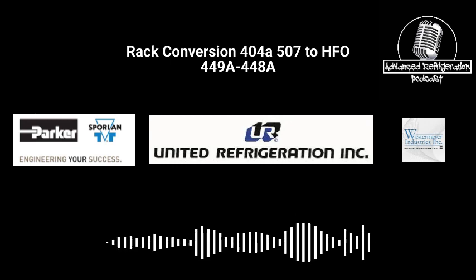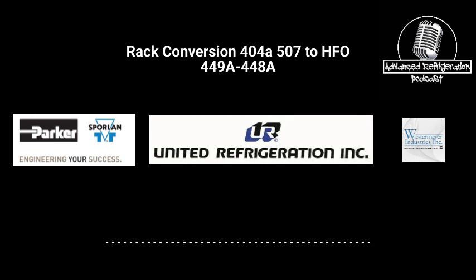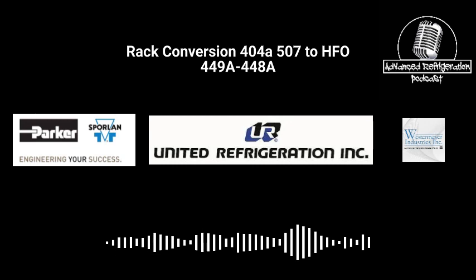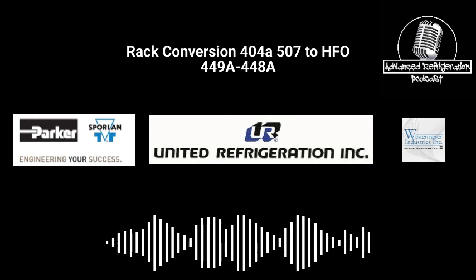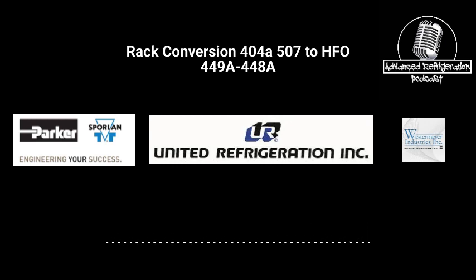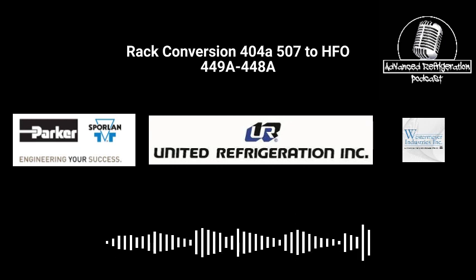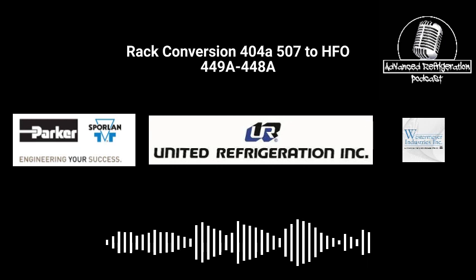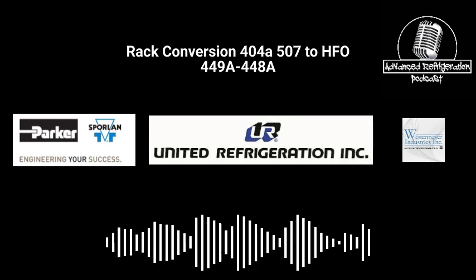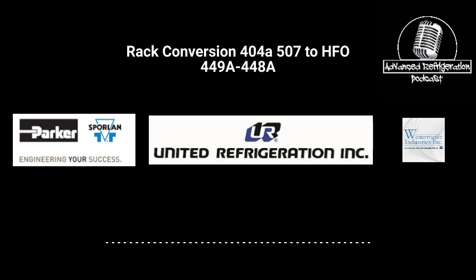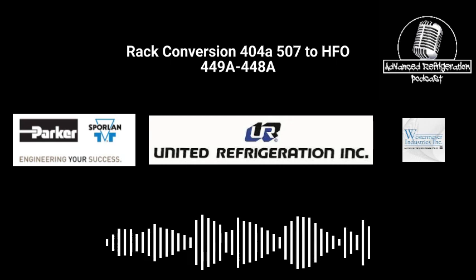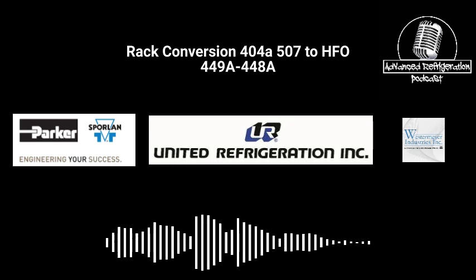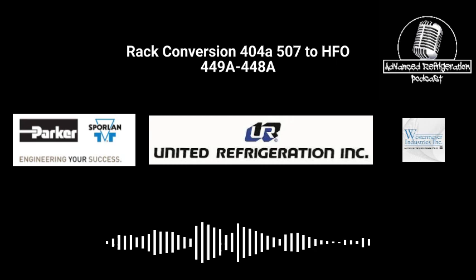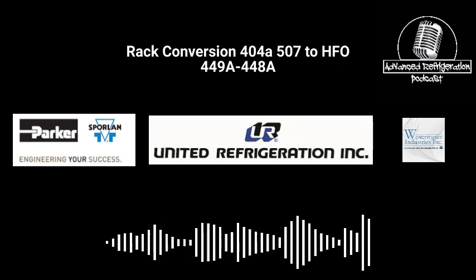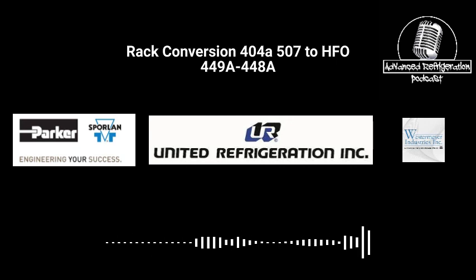We have a store that's actually getting shut down today. It's one of those Walmart stores that got shut down. It had a moisture problem, like really, really bad. Underground piping had a small leak, and it had a habit of burning out the suction transducer. So the home office would force it on, and it would run into a vacuum and suck water. Then you'd spend all this time getting the moisture out with dryers, and you'd just get random service calls. It was awesome, free overtime, because you'd just go there, dump a bucket of water on the valve, and it would take off.